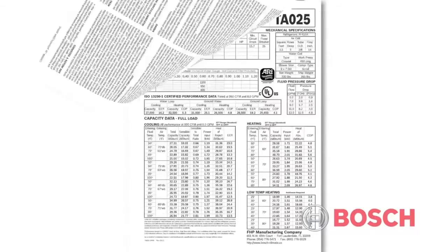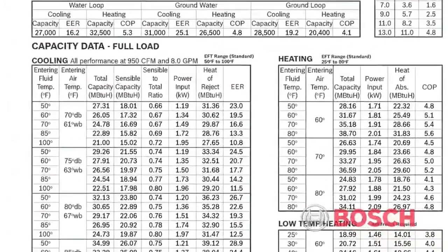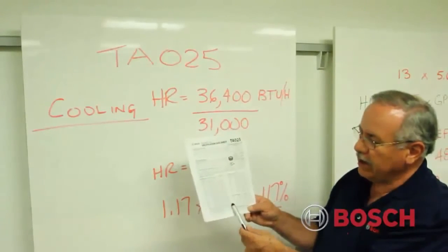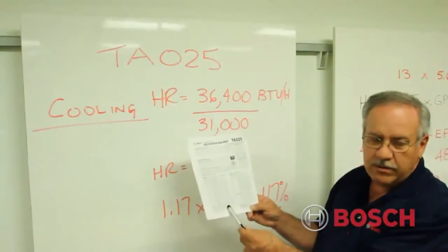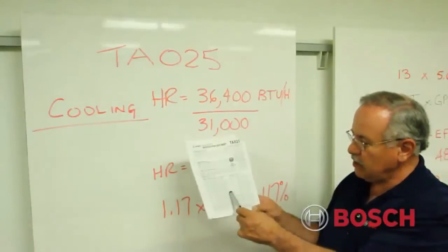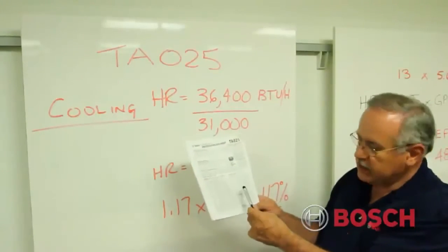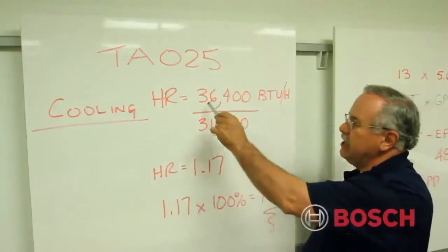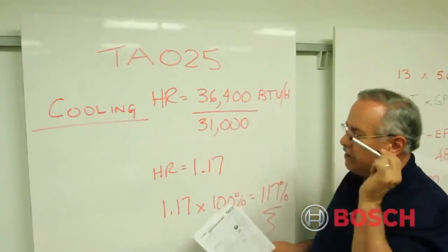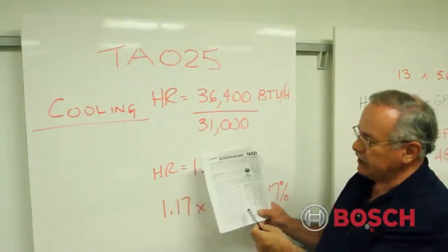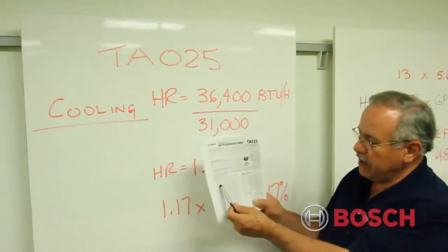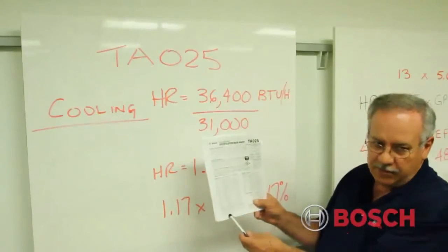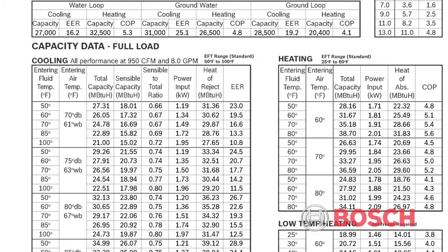Now we go to the specification data, which I referred to earlier, and down here on the lower right of the TA025 page, in full load is capacity data, full load cooling. One of the columns is labeled heat of rejection, MBTUH, thousands of BTUs per hour. Now we're talking about cooling, so we'll use this as the data to compare what we found against. Now if we had been in the heating mode, heat of absorption, we'd simply go to the right over here. Same formula, same calculation methods. So in our particular case, he determined 36,400 was actually being absorbed and rejected from the house into the earth. And if I look at the data, what closely represents the conditions we were under, which fall under entering fluid temperature, entering air temperature, dry bulb and wet bulb, and entering GPM, or GPM flowing through the heat exchanger, I have determined from the specification data that we should be operating at close to 31,000 BTUs per hour of total heat rejection.